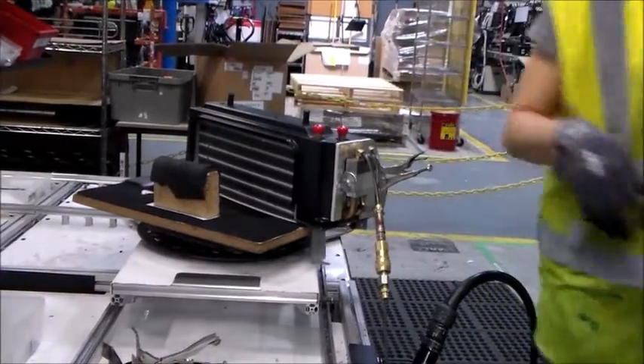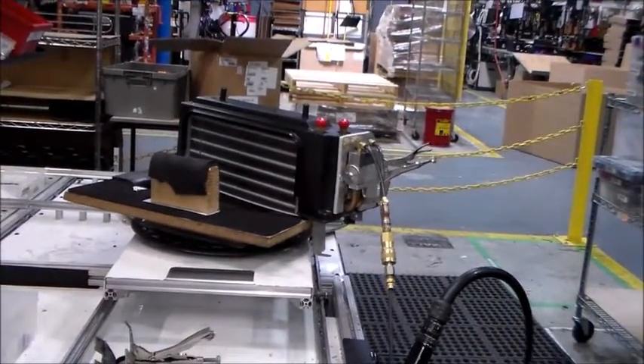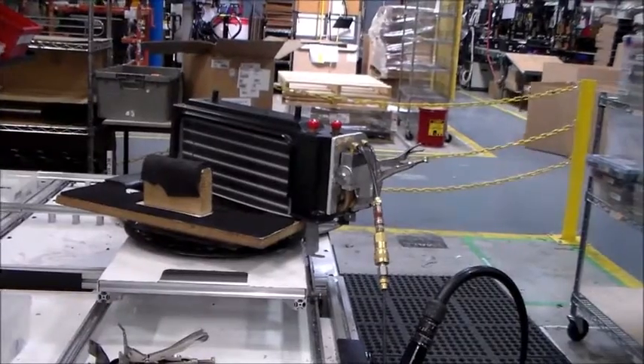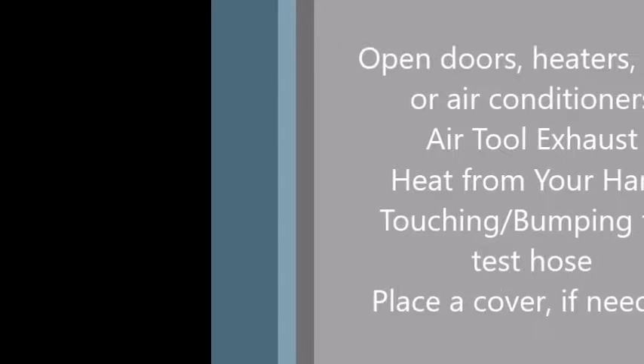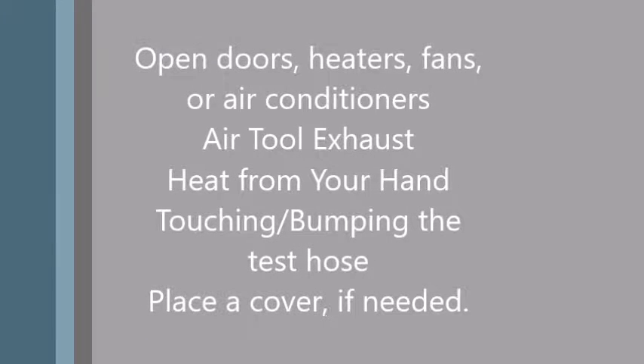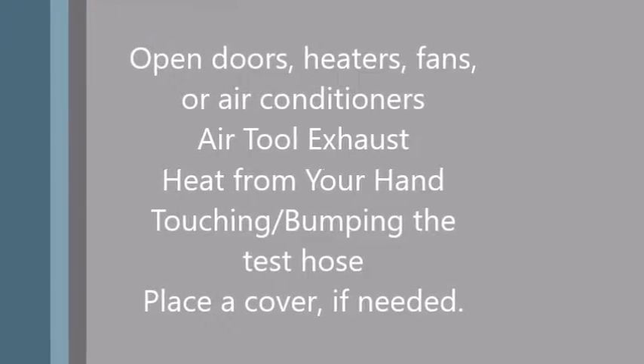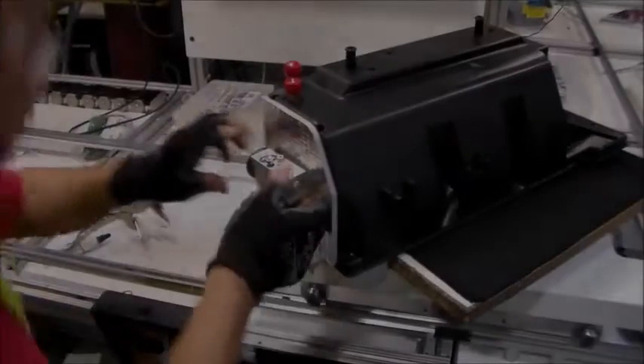Also, a part may or may not pass the leak test portion of the sniffer test because of the environment you are testing in, so ensure there is no excessive air movement near the test part. This includes movement like cold breezes from open doors, heaters, fans, or air conditioners blowing air on parts, or air tool exhaust. Even heat from the operator's hand can cause the part to fail. Avoid touching or bumping the testing hose during the test. Placing a cover over the unit can also help if there is too much air movement.